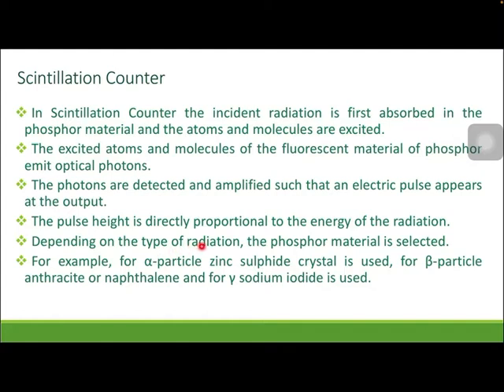Depending upon the type of radiation, the phosphor material is selected. There are a number of phosphor materials which scintillate or emit light flashes. For example, for alpha particles, zinc sulfide crystal is used. For beta particles, anthracite or naphthalene is used. And for gamma particles, sodium iodide is used.